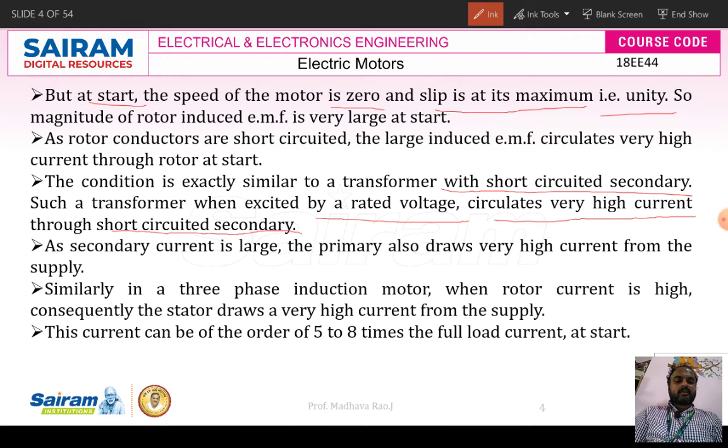Similarly, in a three-phase induction motor, when the rotor current is high, consequently the stator draws very high current from the supply. This large amount of current is approximately 5 to 8 times the full load current. The stator conductors are not able to withstand this much current, 5 to 8 times the full load current. So the stator winding will get damaged first due to 5 to 8 times the full load current, and then the rotor will be damaged.